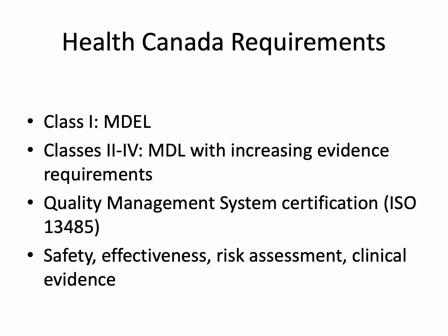Health Canada classifies medical devices into 4 risk classes, with regulatory requirements increasing with risk. Class 1 devices require only a Medical Device Establishment License, MDEL. Classes 2 to 4 require a Medical Device License, MDL, with Class 4 requiring extensive clinical evidence.